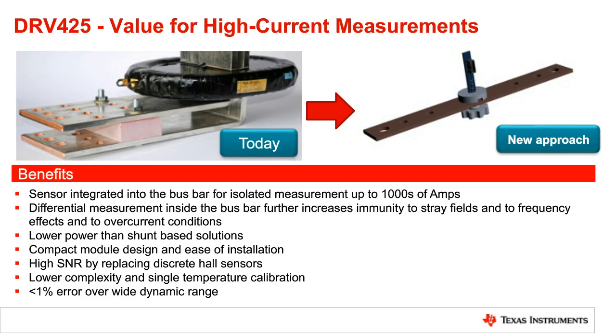Looking at measuring something in the 200 to 400 amp range output of an EVSE, whenever we parallelize all of those power stages and look at the total system output, something like this can fit very well, especially as EVSEs start growing in power output. And even with the amount of current and the size of this solution, we're still able to see less than 1% error over a very wide dynamic range.